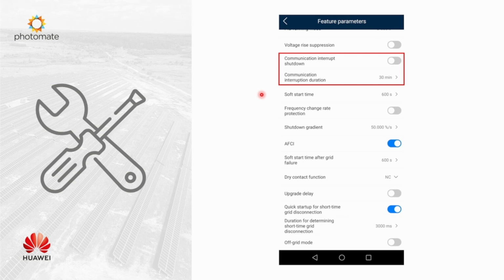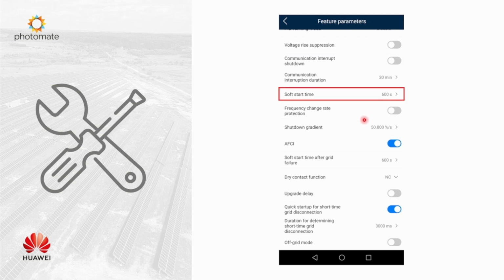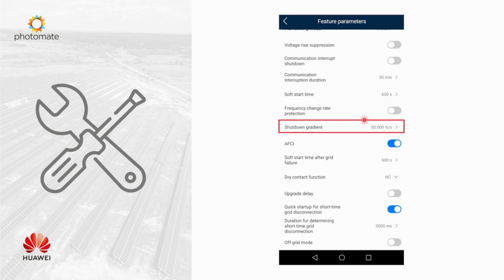So this is the menu, how it looks like. I mean, when you open it and when you can enable and disable those functions. Some of them also need to be explained. Communication interruption shutdown. In some countries, when you have a problem with the communication with the inverter, it must shut down, and you can set, of course, some time limit when it must happen. Soft start time, this is obvious, the name tells you everything. Shutdown gradient, how fast your inverter is shutting down. In that case, it will take 2 seconds to reduce the power to 0.